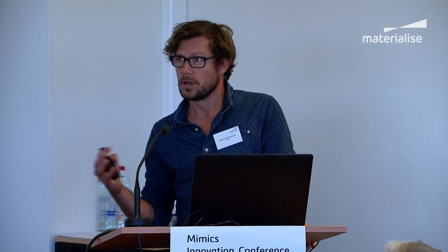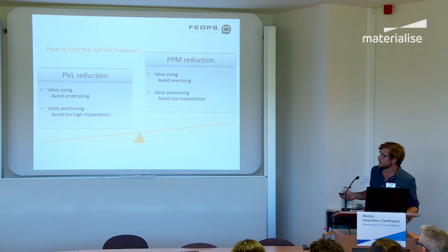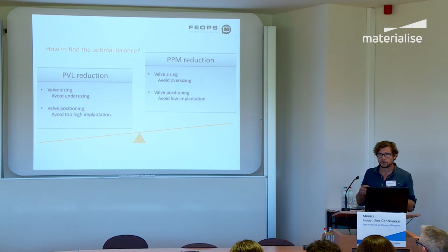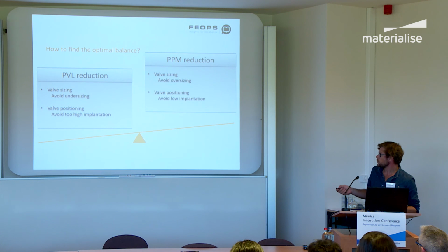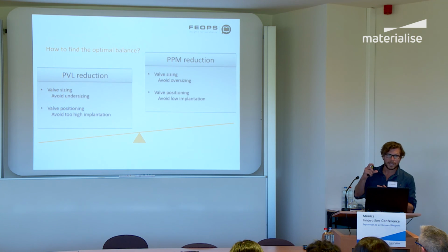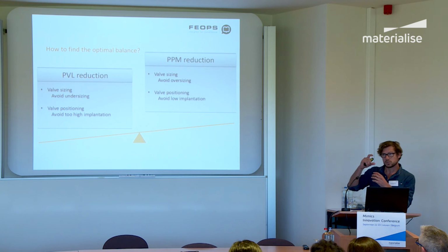Now, if you look from a very simple point of view, why is this occurring? Well, because you have two counterindicating factors here. If you want to reduce PVL, you should try to do two things. One thing is, of course, you should try to avoid undersizing. If your device is too small, for sure it will not appose well, and you will have leakage. What you also try to avoid is too high an implantation depth. If you position the device too high, then again you have more risk of leakage.